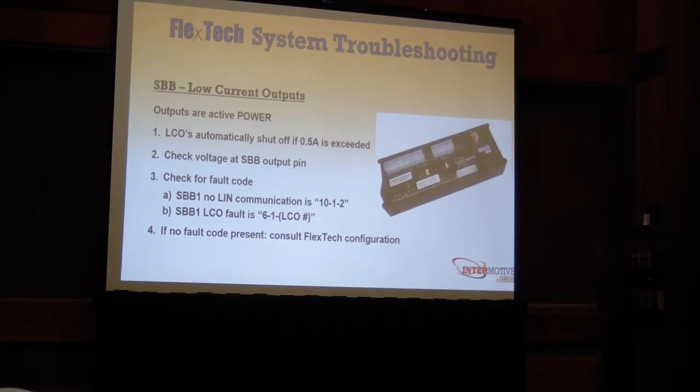If there's no fault present, it's possible that we don't completely understand the logic that's required to turn that output on. So we'll need to get the FlexTech configuration, consult that, and make sure that we're getting all of the conditions right for that output to come on. And we'll look at breaking down a configuration. I'll go over a configuration summary and how to break down the logic for an output.